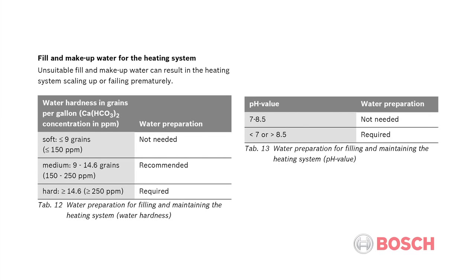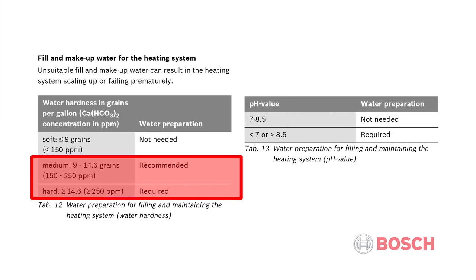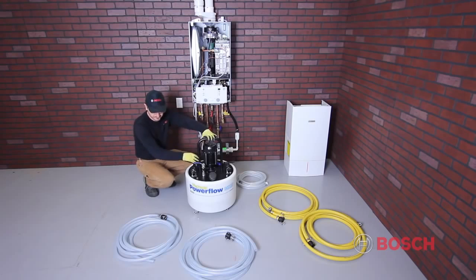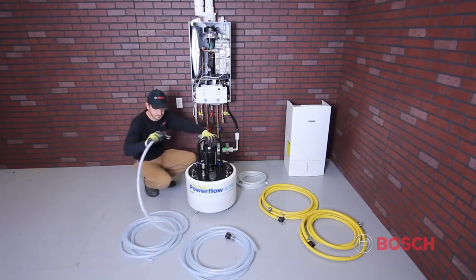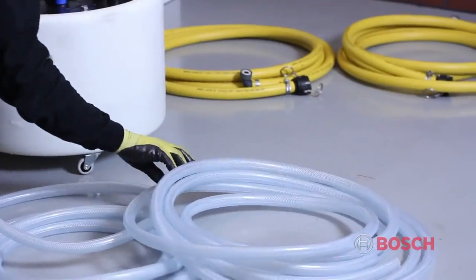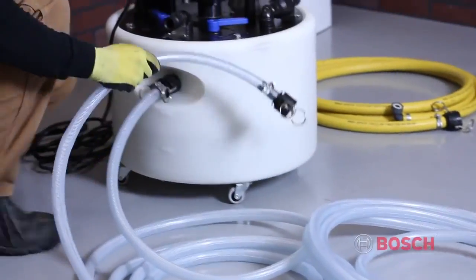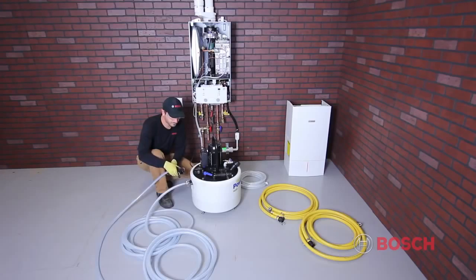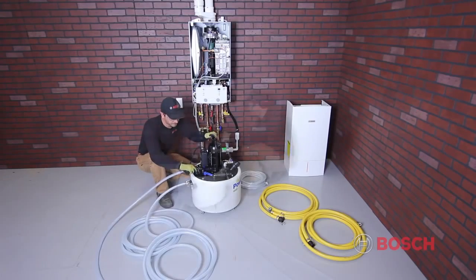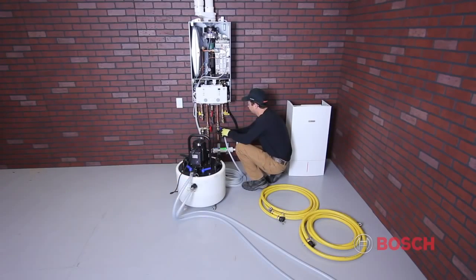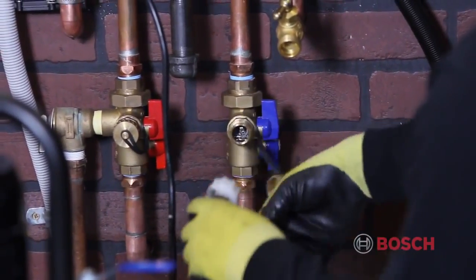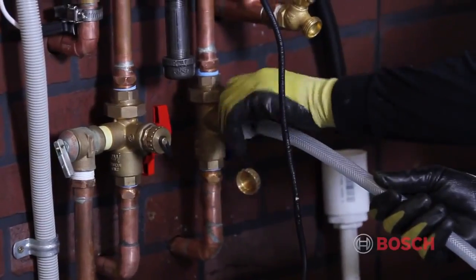Always treat your fill and makeup water when the water hardness is above 9 grains of calcium carbonate per US gallon and the pH value is less than 7 or greater than 8.5. Cleaning and treating a heating system, even a new one, will increase the performance, reduce fuel bills, and extend the life of the boiler and associated components. Cleaning the system will remove flux, solder, excess pipe dope, cutting oil, and other impurities that can reduce system performance.